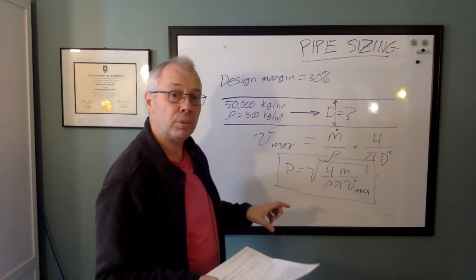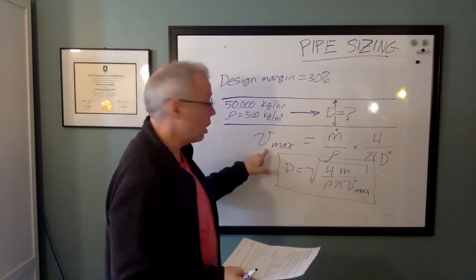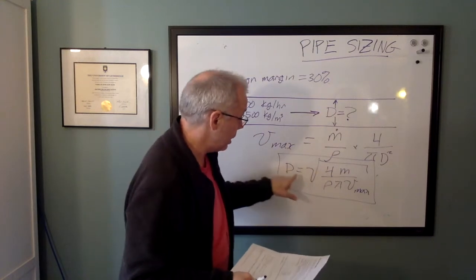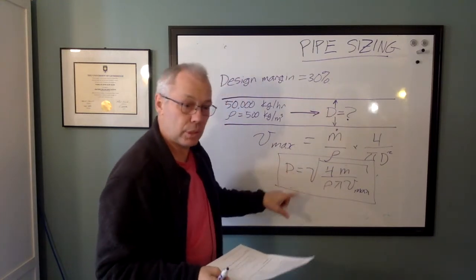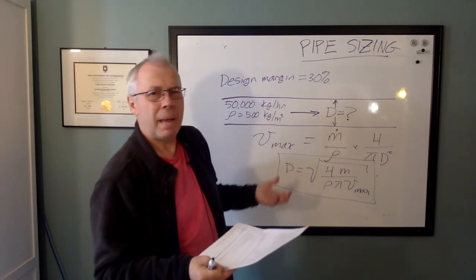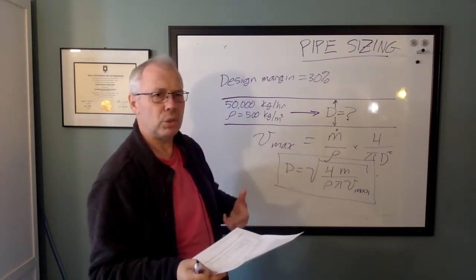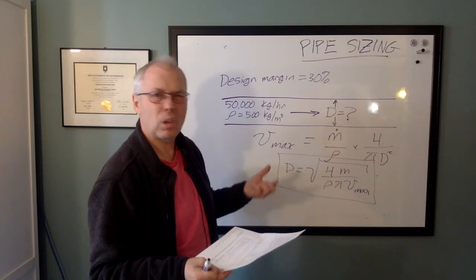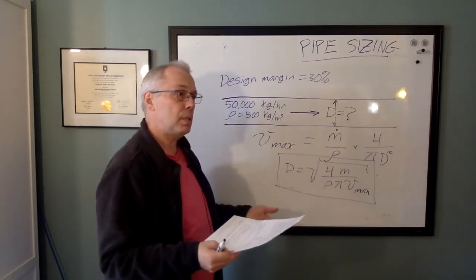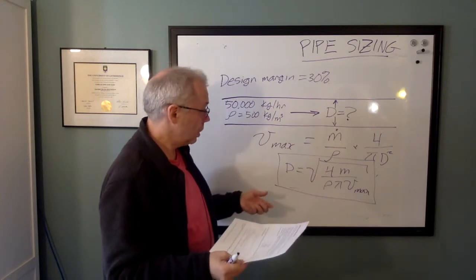So someone could say, size it for a maximum velocity of three meters per second, and you can go through the math and you can say that's the diameter. But there's nothing magic about three meters per second. Is it good for erosion? Couldn't tell you. It's a common number. If it's a vapor, it might be 30 meters per second.